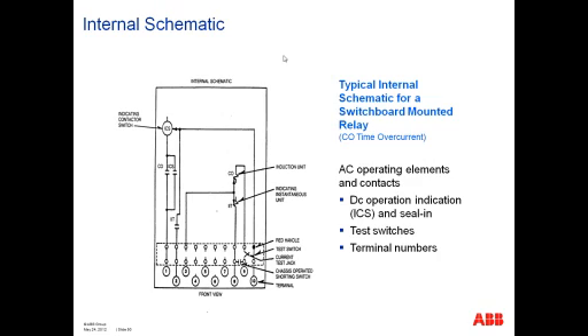Typically I don't show too much of this, or you don't see a whole lot with more modern relays, but you do have a real large installed base of electromechanical relays. So I'm showing you some electromechanical internal schematics. Each electromechanical device has an internal schematic that shows you the coils that operate, like the induction unit and the indicating instantaneous unit. There may be a directional unit. There is an indicating contactor switch which operates whenever the relay operates to give you a target, because in those days we didn't have everything on digital fault recorders, and you had to depend a lot on these indicating contactor switches to get information about what operated and did not operate.